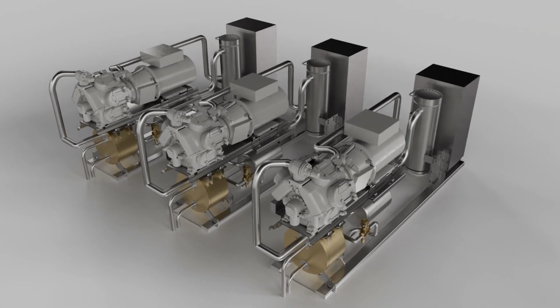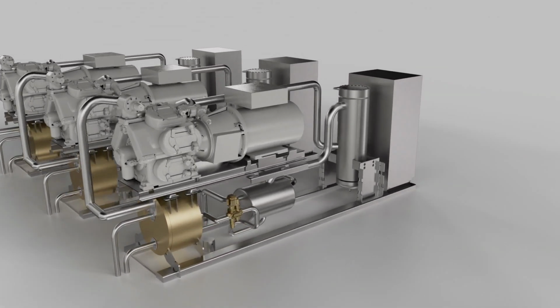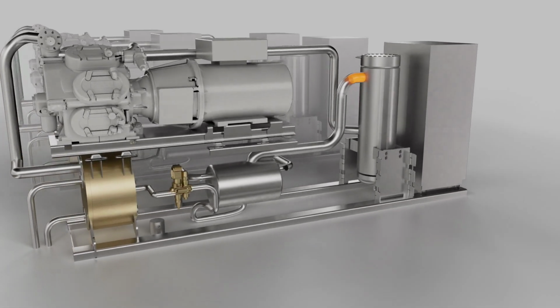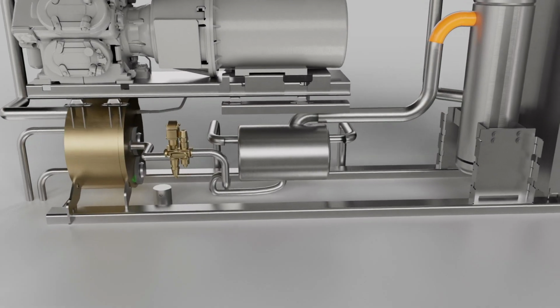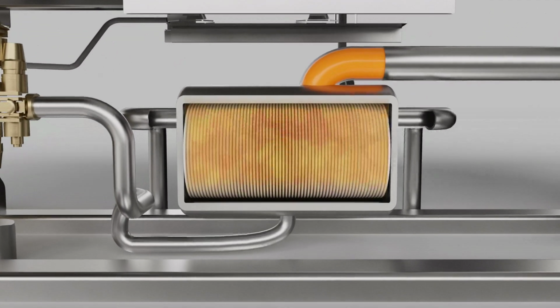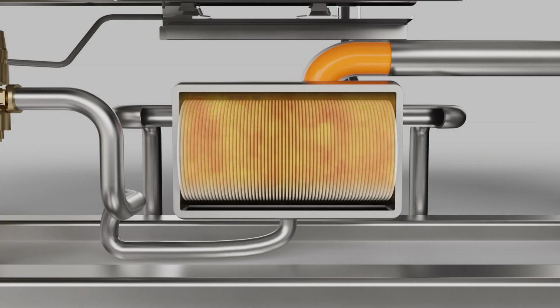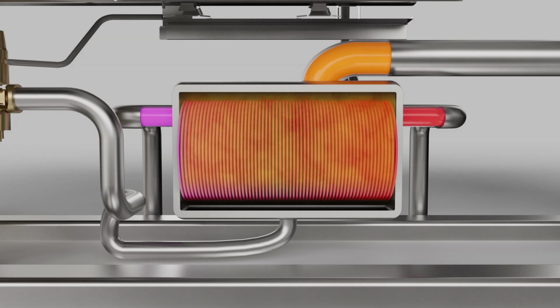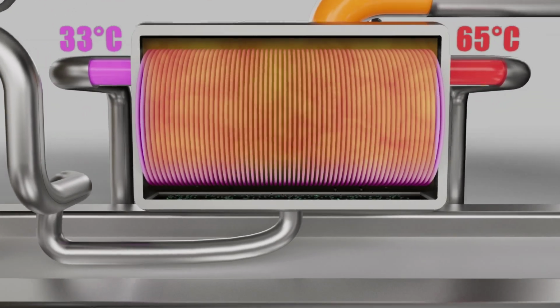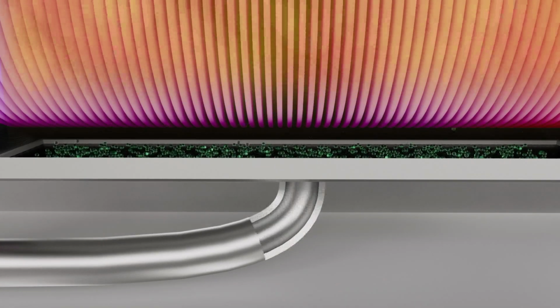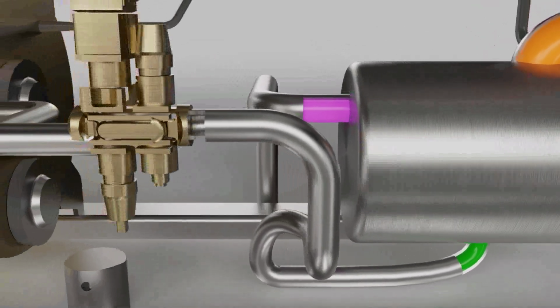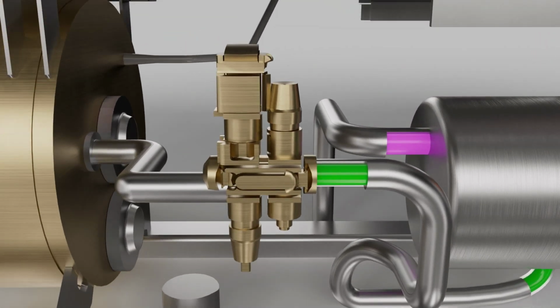The 3 heat pumps all work according to the same principle. Hot ammonia flows into a special heat exchanger, the so-called condenser. Here the gas transfers heat to a water circuit via a heat exchanger. The water is heated by the hot gas to 65 degrees Celsius. Depending on the requirements of the system, from around 33 degrees to up to 65 degrees Celsius are possible. The ammonia cools down and liquefies. The liquid flows through a valve. Since there is less pressure behind the valve, the ammonia cools down.